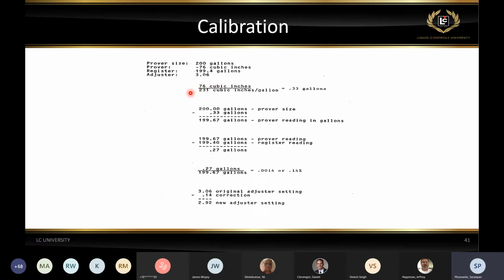The first thing we're going to do is convert the cubic inches to gallons. So 76 cubic inches divided by 231, that's the number of cubic inches in a gallon, equals 0.33. So 200 minus 0.33 gives us a prover reading of 199.67. Now we have a prover reading and a meter reading, we can calculate our error, which ends up being 0.14%. Since the prover is reading more than the meter, we're going to take the current adjuster setting of 3.06, subtract our error, giving us a new adjuster setting of 2.92.